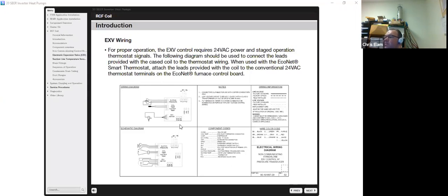So basically down here you'll see the connections: your suction pressure transducer, your coil temperature sensor, your EXV motor, the 3 dip switches, and here you have R, C, Y1, Y2. Excuse me, you'll notice you don't have an E1 or E2 here. So basically you have 4 wires that will go back to your furnace control board. One will tag into your R, one will tag into your C, one will tag into the Y1 terminal of your control board, and one will tie into the Y2 of your control board. So this is looking for more 24-volt signals than a true communication, like you see in the air handler.